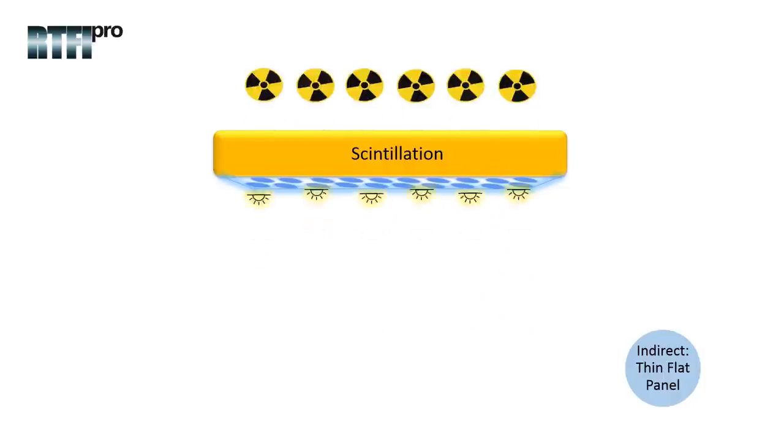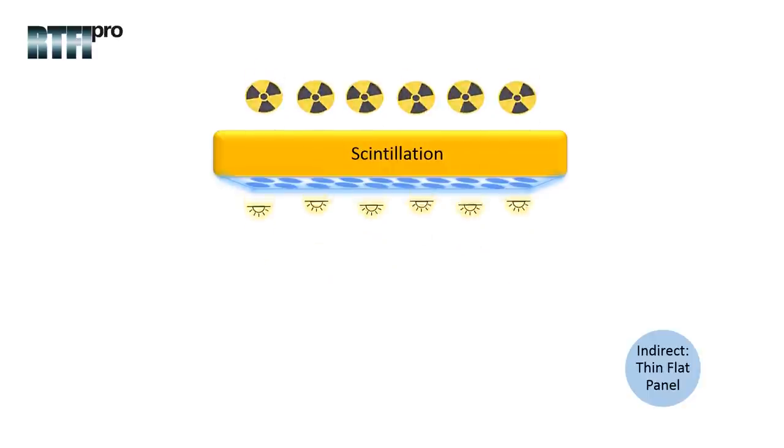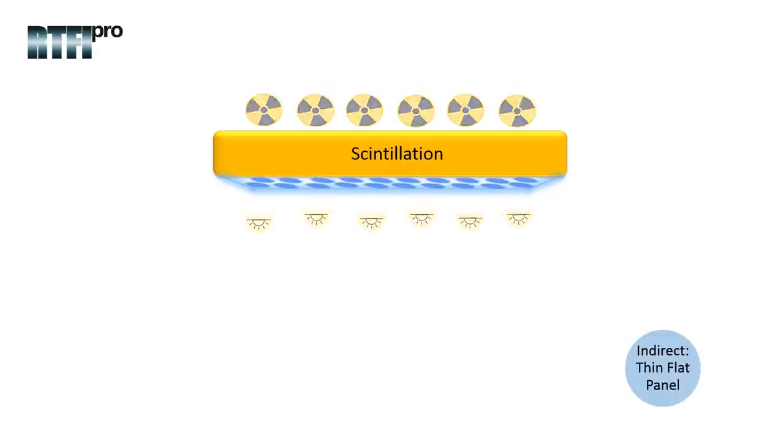The distribution of light in all directions, known as isotropic diffusion, does have a negative impact as it decreases the spatial resolution because the size of the converted light photons are larger in size than the incoming x-ray photons, which result in a small definition loss within the image.